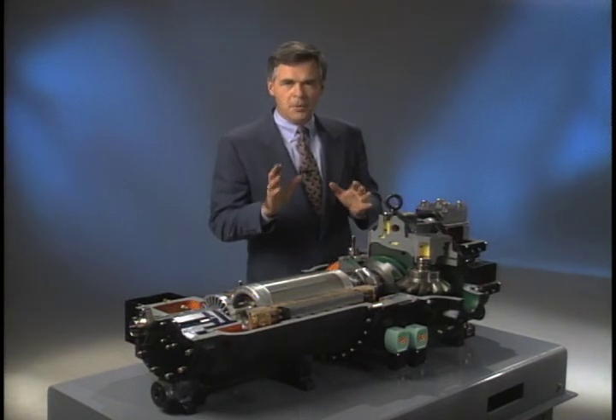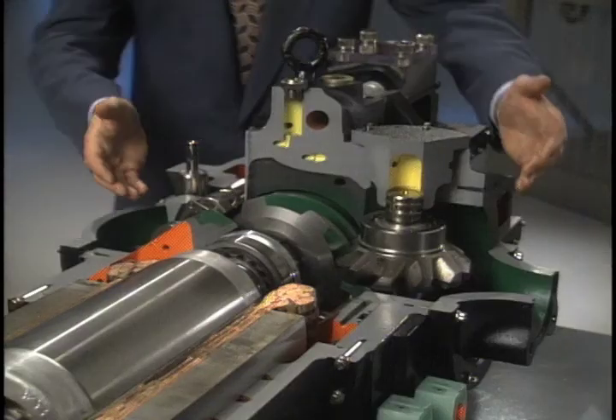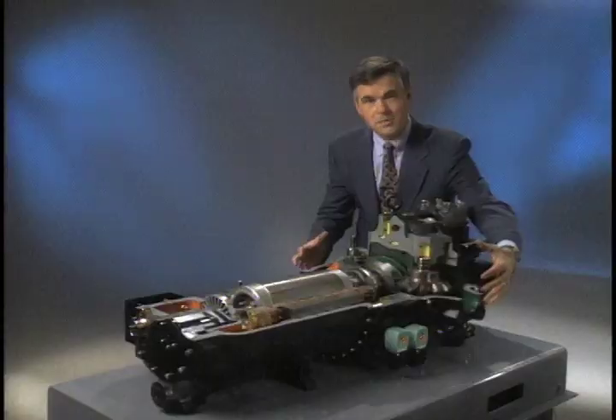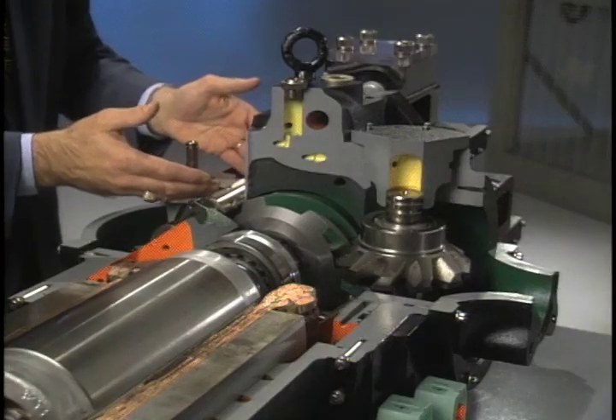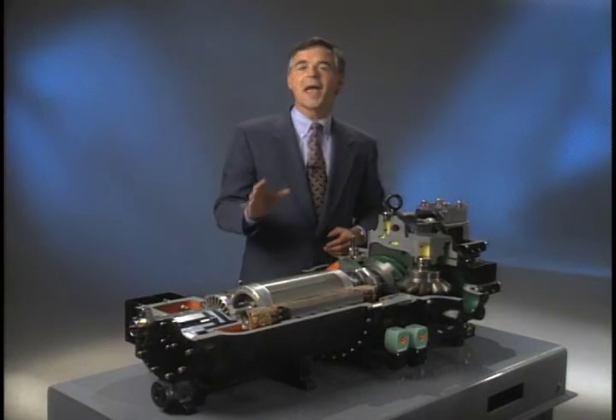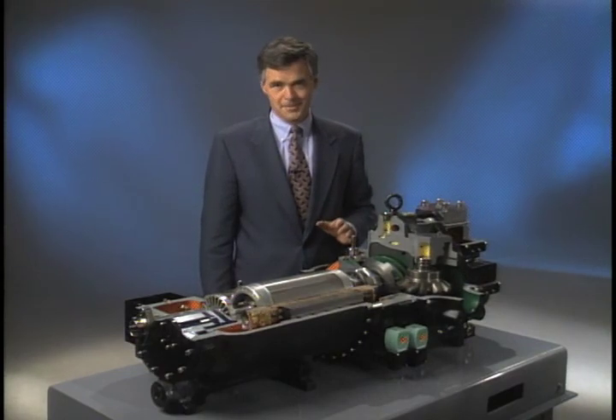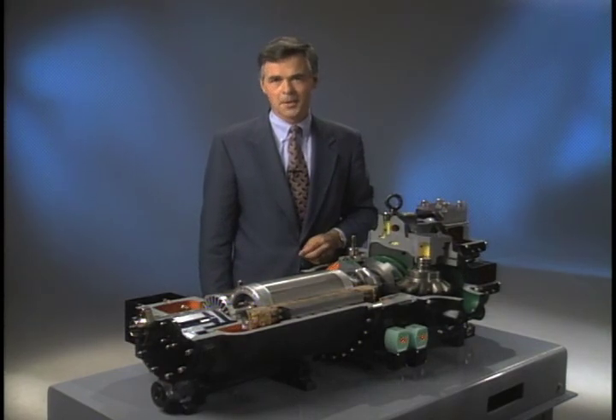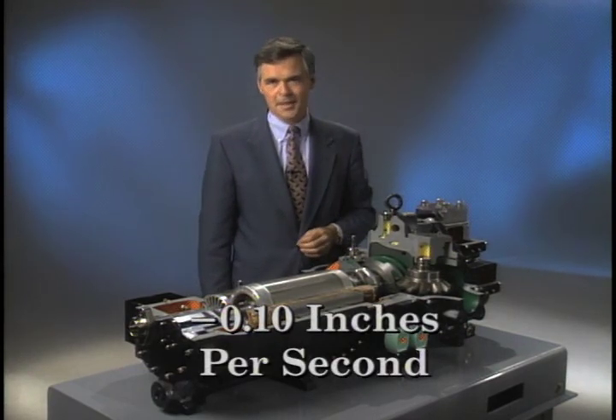Furthermore, this compressor operates balanced, virtually load-free, because compression occurs on both sides of the main screw simultaneously, while both ends of the screw encounter suction pressure only. There are no heavy radial or axial loads ever. Little wonder the Stargate is so quiet. It's a perfectly balanced compressor, one that reduces vibration to less than 0.1 inches per second, barely a hum. One that transmits almost no movement to refrigerant lines and other parts of the system.